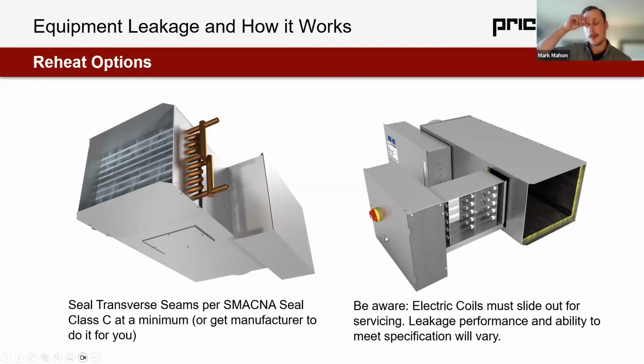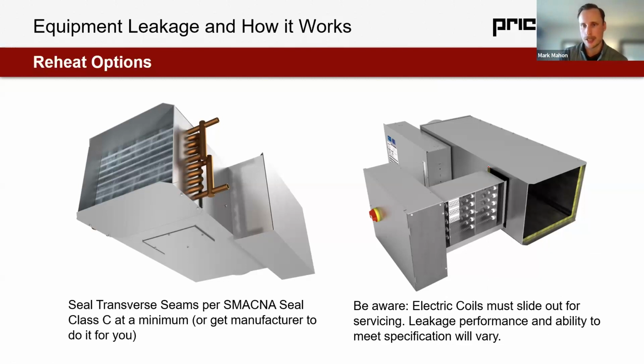My note to any engineers who utilize electric coils is to be aware, because electric coils and duct mounted heaters of any kind, whether on a single duct or just in the ductwork, need to slide out for servicing. That means leakage performance might vary. At Price, what we do to manage this is gasket. We can gasket around the seam as an option. Generally, that isn't something we see specified or required frequently.